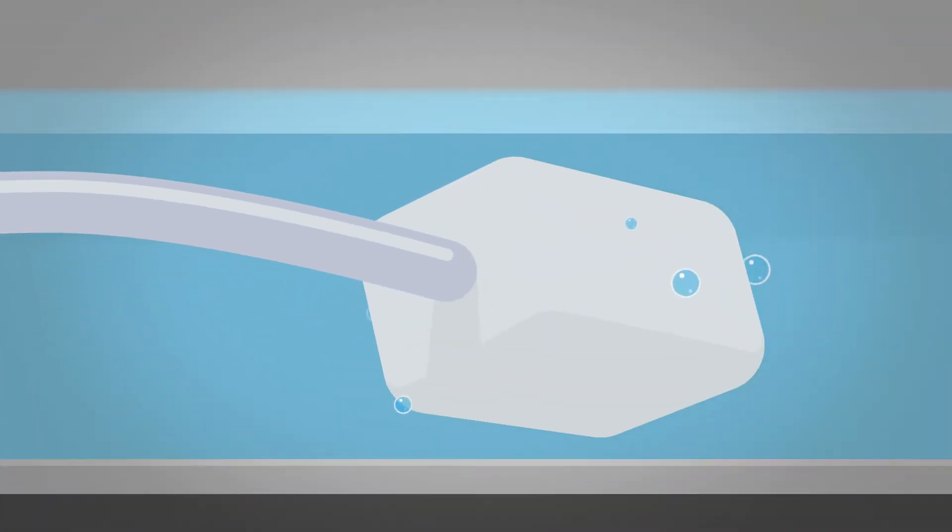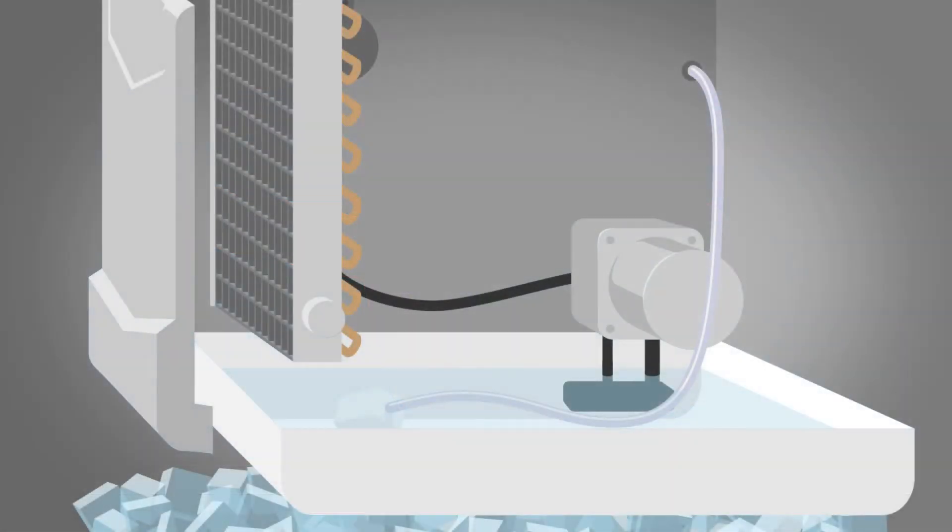Ozone is delivered to the sump through a diffuser stone. Bubbling ozone through the sump water gives the ozone an opportunity to keep the water and wetted surfaces clean. The remaining ozone off-gasses into the chiller compartment.